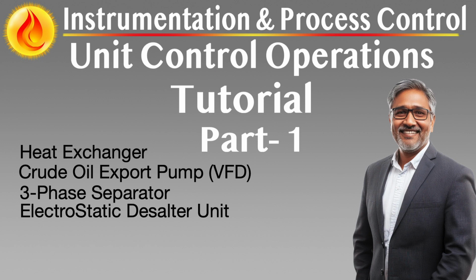Feed-forward control has gained greater traction in heat exchanger applications, particularly where disturbances such as fluctuating inlet temperatures or flow rates are measurable. These strategies use predictive logic to adjust utility inputs preemptively, improving disturbance rejection. When combined with feedback control, this hybrid approach significantly enhances robustness. Simulation tools integrated with control system software allow engineers to design and validate these strategies against dynamic load profiles before plant deployment. Digital twins have further revolutionized heat exchanger control.